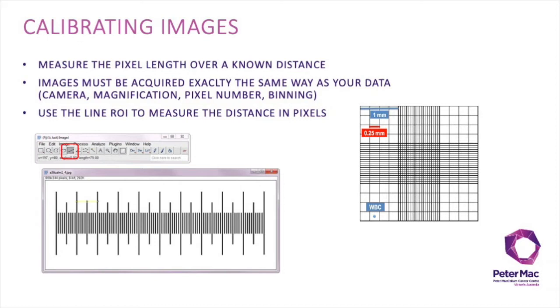One question we regularly get is: how do you know what the pixel size is to calibrate the image? There are special calibration slides available, or you can use something like a hemocytometer slide, which has defined distances. If you capture that distance information in the exact same way you acquired your data, you can use the Line Region of Interest tool to draw across the known distance, giving you the length in pixels, and then calculate the pixel size.